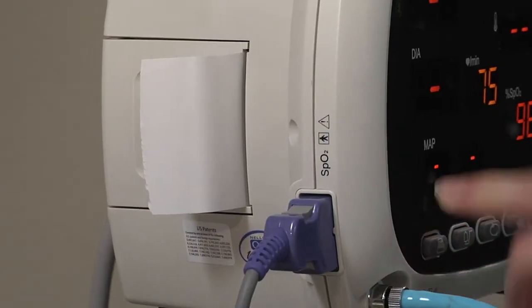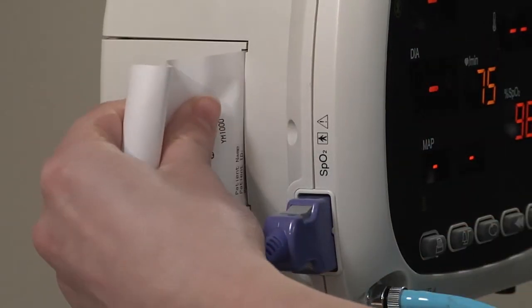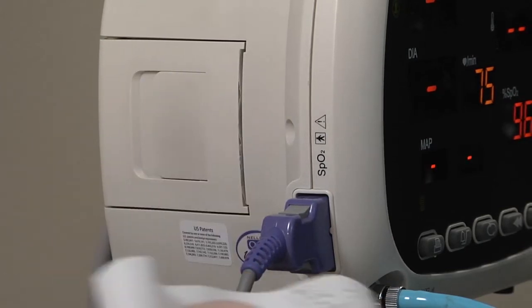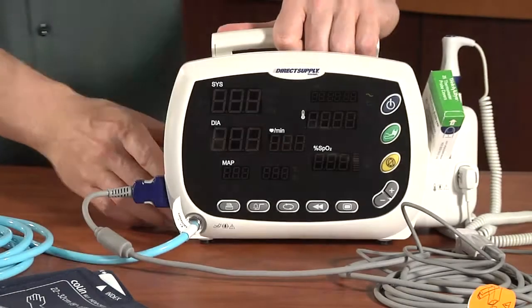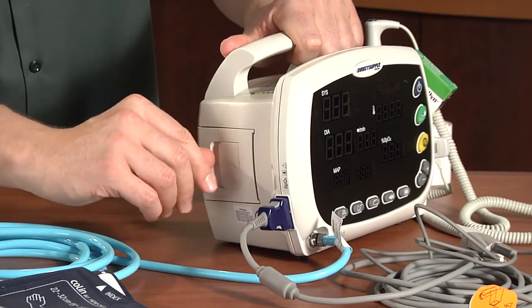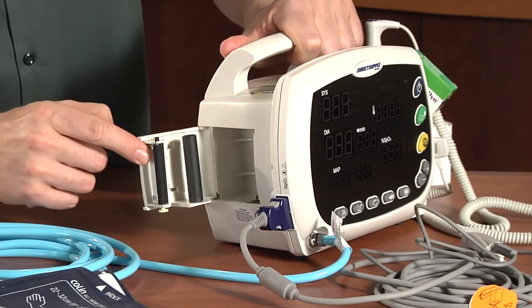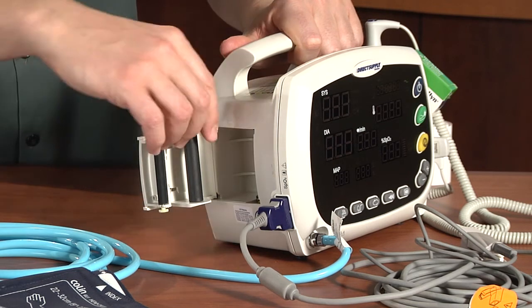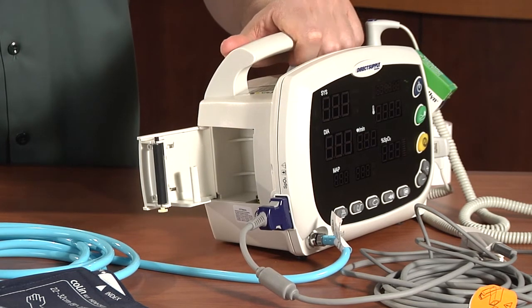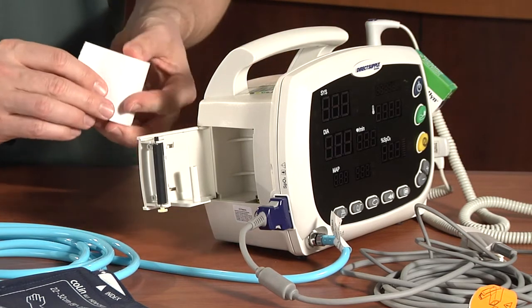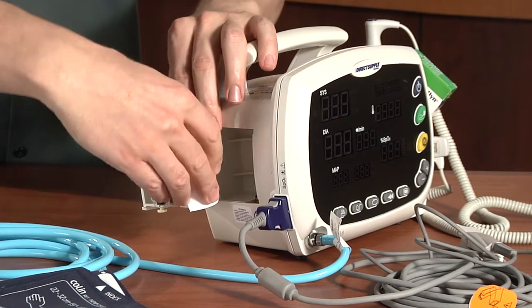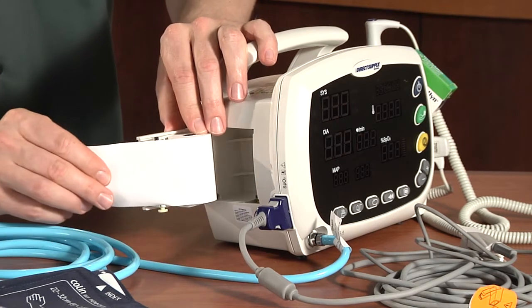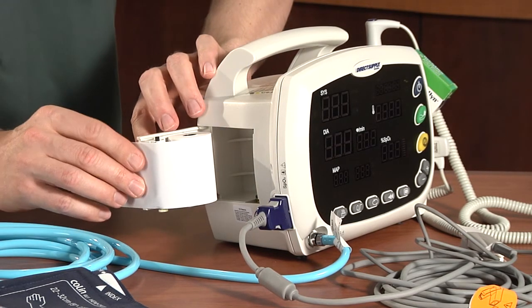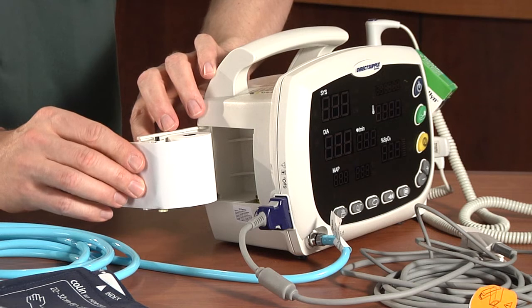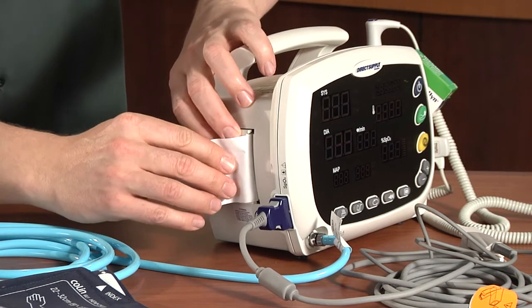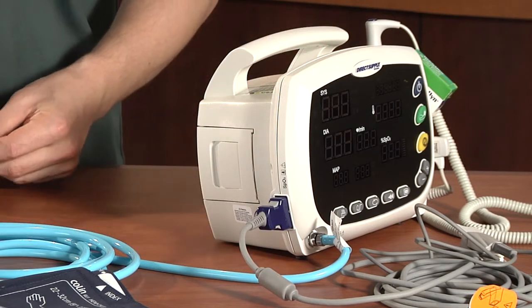Your Attendant Vital Signs Monitor may come with an optional printer. To replace the printer paper, follow these simple steps. First, open the door by gently pulling on the printer latch on the left side of the unit. The door should tilt open. Reach in and remove the empty paper core by gently lifting it with your thumb and index finger. Insert a new paper roll and ensure the paper roll is properly aligned as shown. Pull the paper towards you until approximately 2 inches of paper have been unrolled. Align the paper with the paper attached to the printer door and close the printer door.